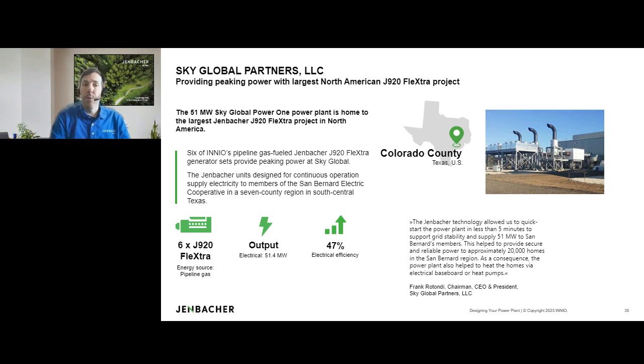They were really reliable during Winter Storm Uri a couple of years back, when, as many of you probably know, there were widespread outages in the electric grid and also the gas grid. They were able to run these units continuously during that week. They had a local reliable gas supply, and they were basically feeding 50 megawatts back into the grid during that time, which was helpful for the customers, and also financially very attractive to the owners of this site, being able to operate at those very high rate hours during that one week in February.